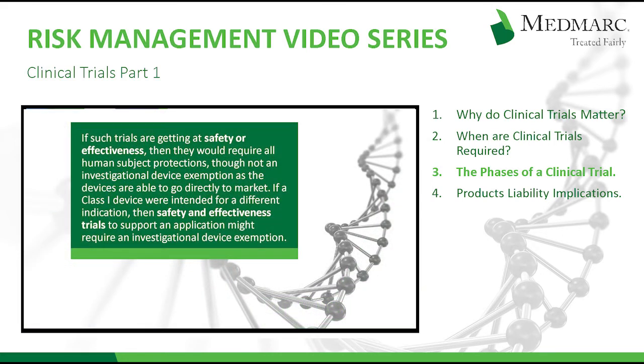However, Class 1 manufacturers may wish to conduct clinical trials to gather data to support marketing claims they intend to make. If such trials are getting at safety or effectiveness, then they would require all human subject protections, though not an investigational device exemption, as the devices are able to go directly to market.